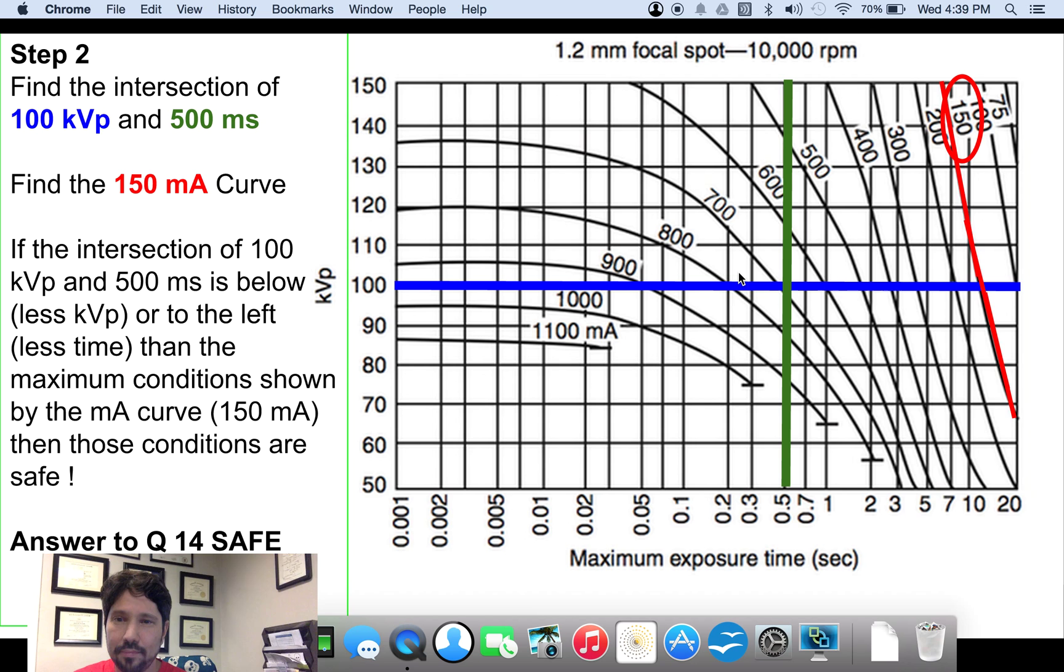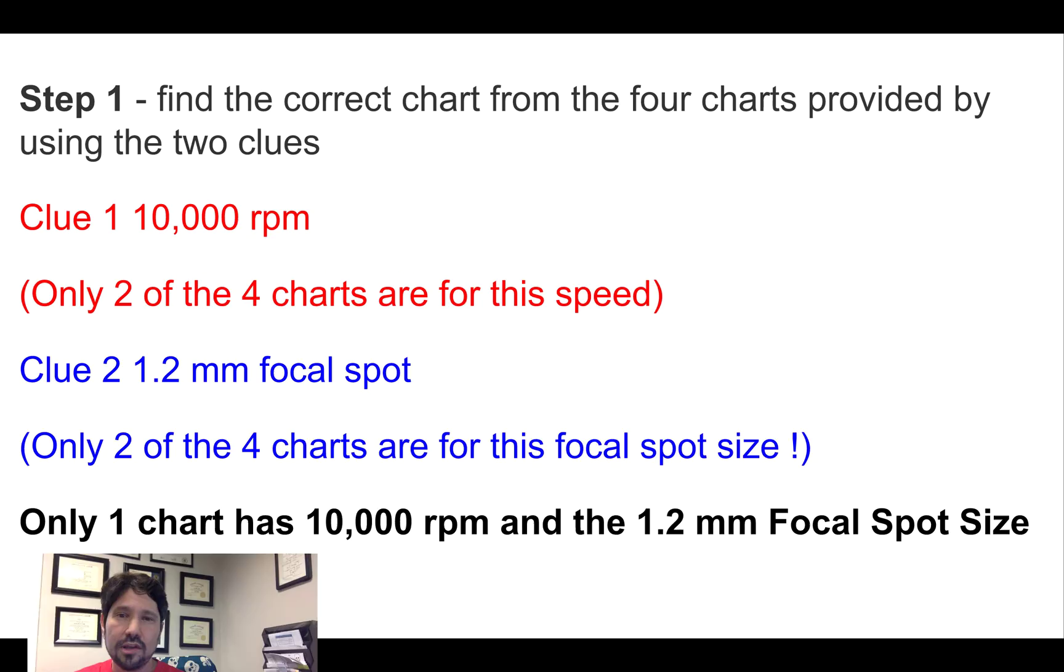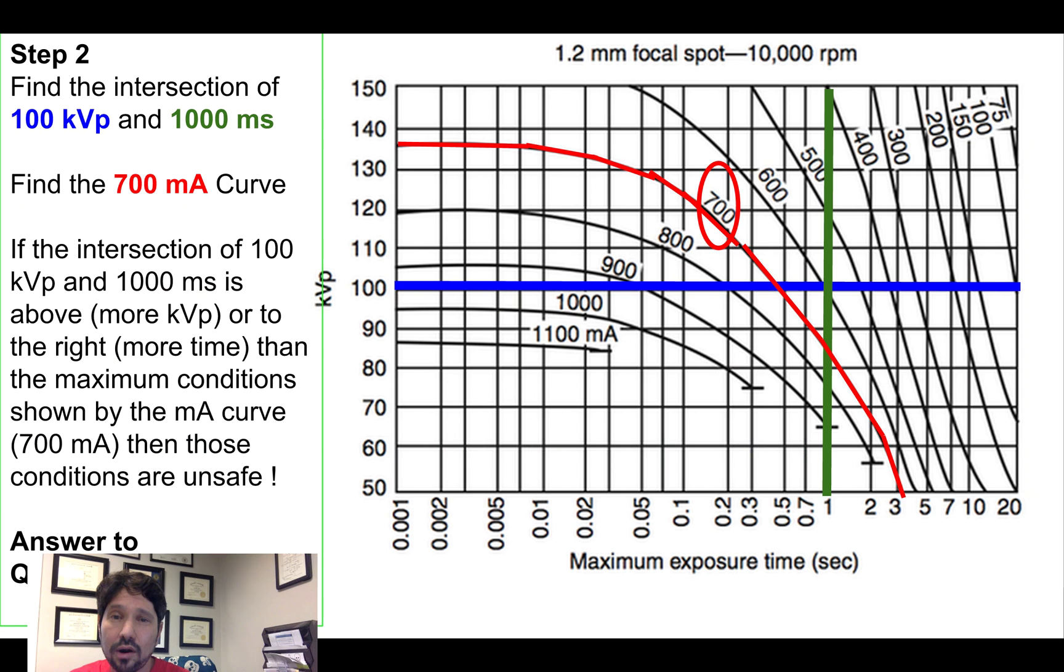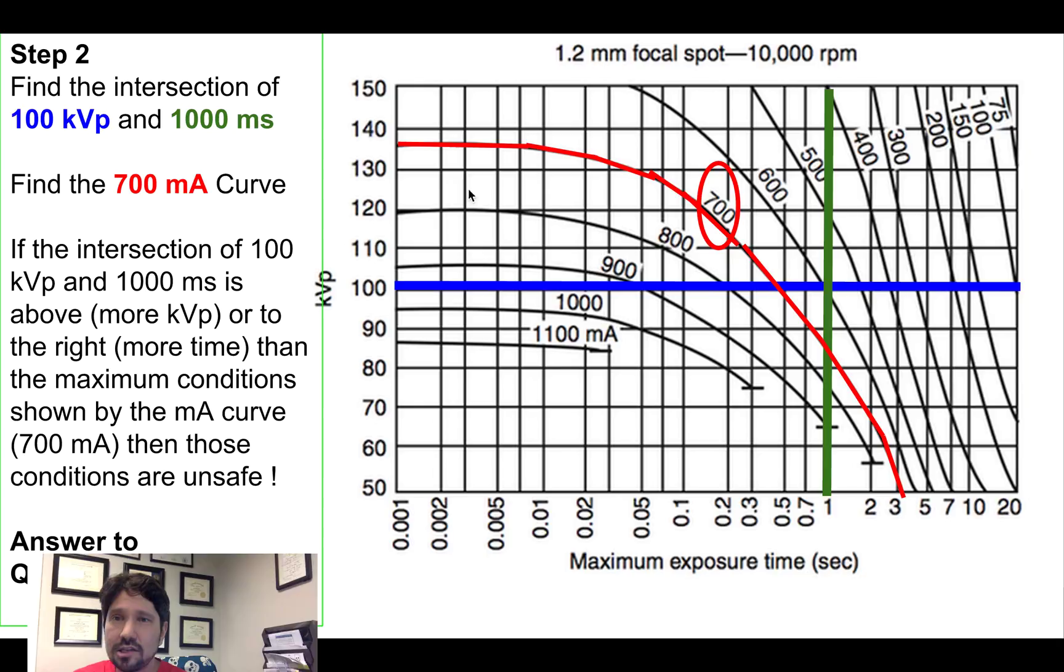So let's do another problem. In this problem, again, they give us the 10,000 RPM, the 1.2 millimeter focal spot, but we've got new conditions. We've got the 700 mA curve. So we're going to find that same graph. It's the same one of the four. And now we're going to draw our blue line at 100 kVp. So that didn't change. But now we're talking a thousand milliseconds, which is one second. So I draw my green line at one second. And here's their intersection.